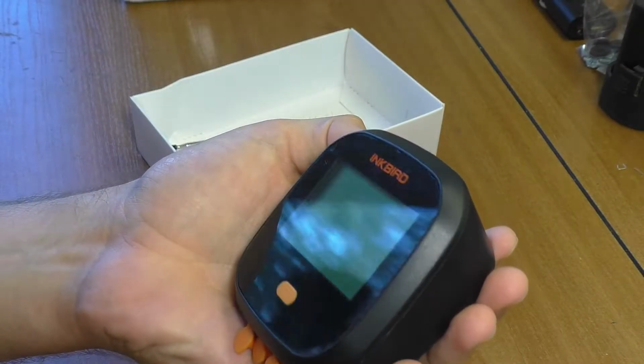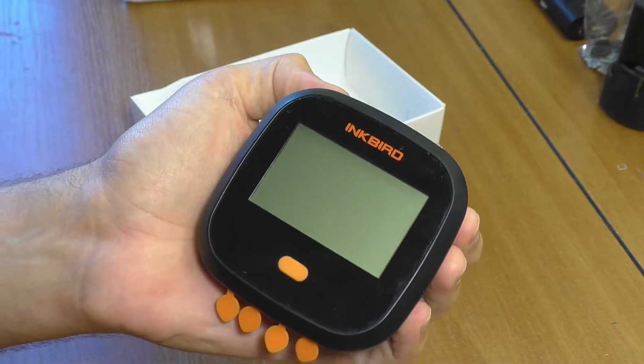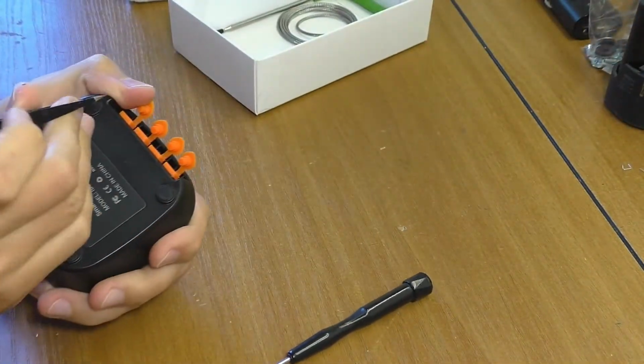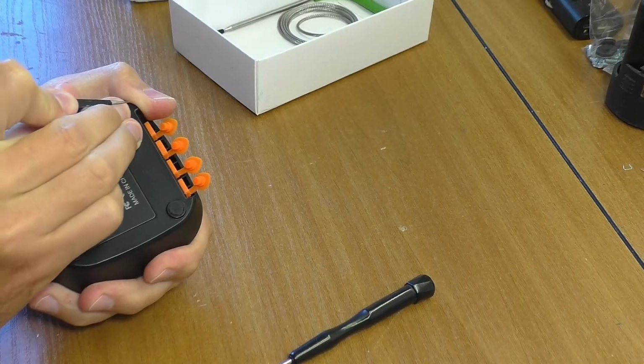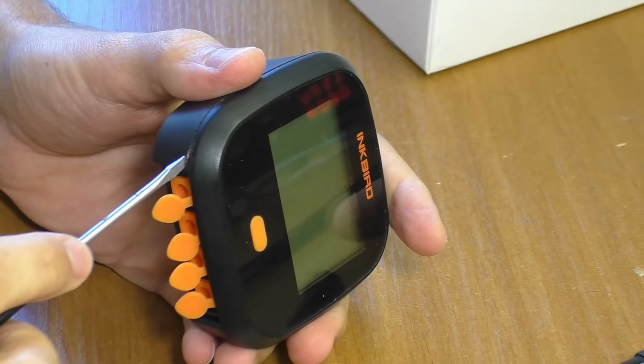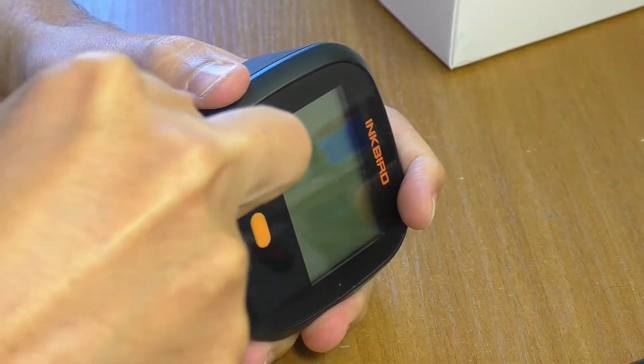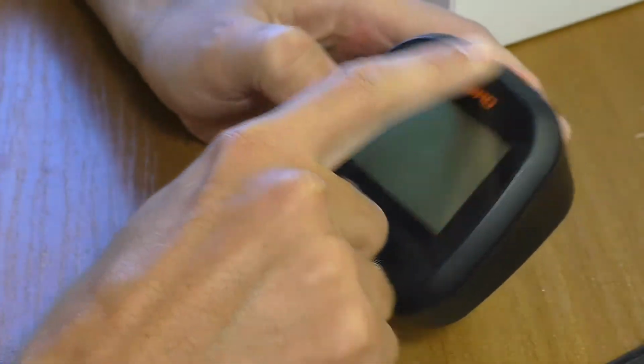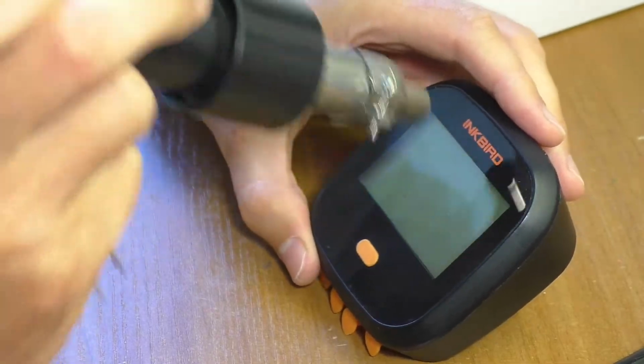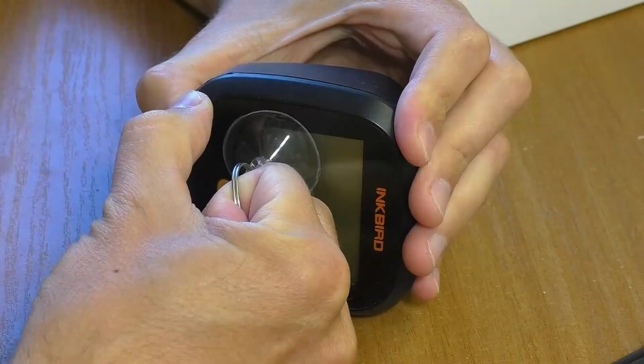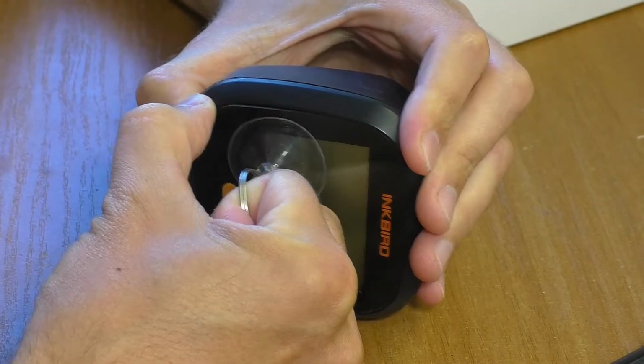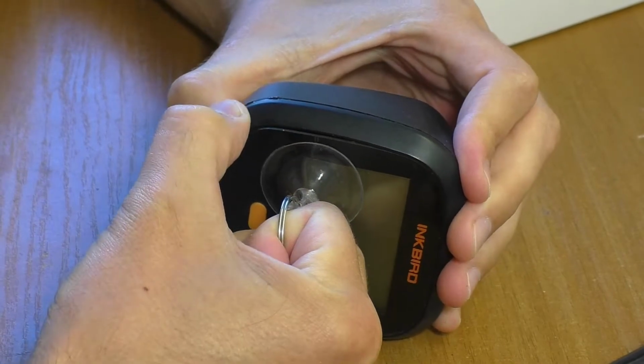In this repair, we will try to figure out what could have happened to this thermometer. Let's start by unscrewing the screws on the case. I couldn't find them anywhere, even under the rubber feet. Well, they still have to be there, because the body is not easy to disassemble. Clearly it is not assembled with latches. All that remains is to peel off the glass by heating it with a hairdryer. The temperature is 150 degrees and it easily succumbs to the suction cup. I didn't even have to pick at anything.